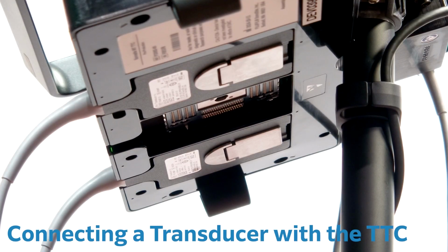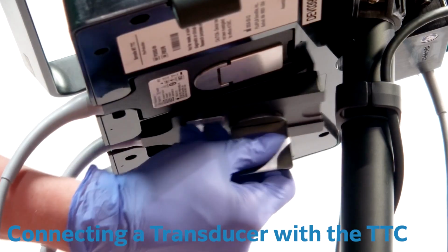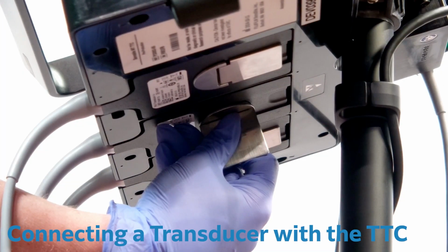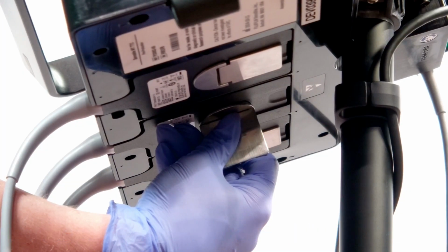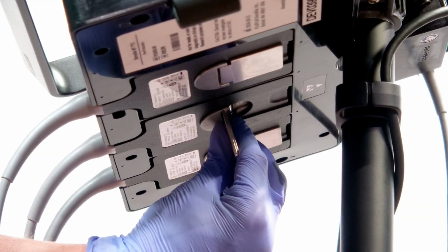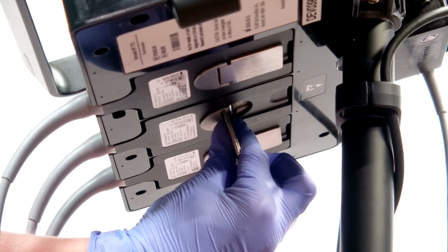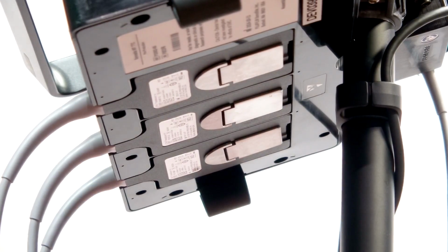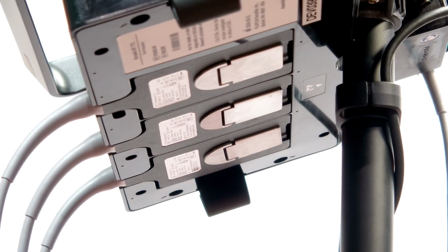To connect a transducer to the TTC, insert the transducer connector into one of the transducer module ports at the bottom of the stand head. Make sure that the connector is firmly seated and then turn the latch handle clockwise. Press the latch handle up, securing the transducer connector to the transducer module.